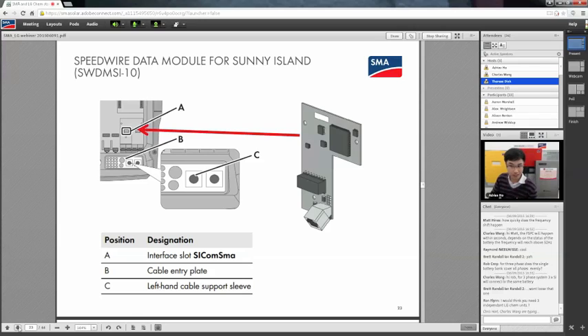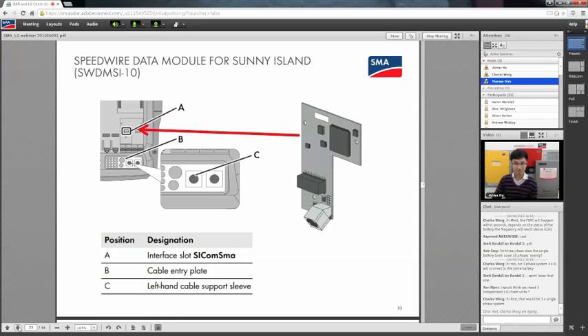The sunny island can now talk in SpeedWire Direct. So for the on-grid storage, you do need the SpeedWire data module, at additional cost of course. The SpeedWire data module is inserted in the sunny island for it to communicate over Ethernet.